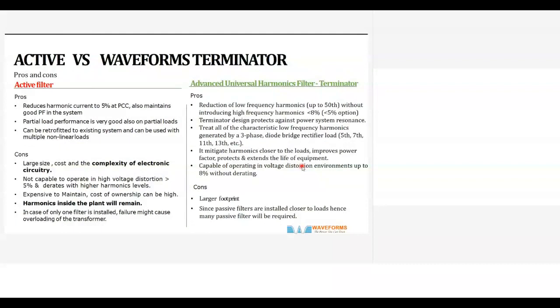So normally active filters closer to loads, in smaller sizes, can become very, very expensive. So normally, to get rid of harmonics and avoid a penalty by the utility, they straight away install it at the MB panel. So the harmonics is reduced at the measuring point, PCC. So there is no issue, you don't pay a penalty.